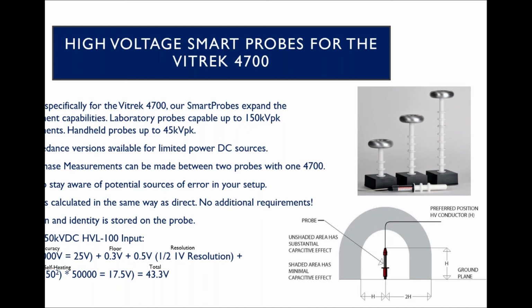We also have the high voltage smart probes, which are for the 4700. They plug directly into the front panel and essentially change how much voltage you're able to measure. So the smart probes really expand that capability of having that direct on-screen measurement up to that 150 kV peak level for a laboratory style probe with a base, or handheld probes up to 45 kV peak. There are also high impedance versions available for DC sources, which may have a limited power capability.